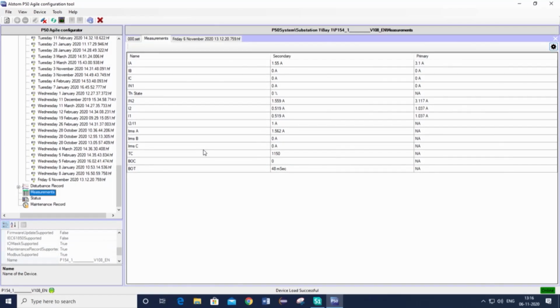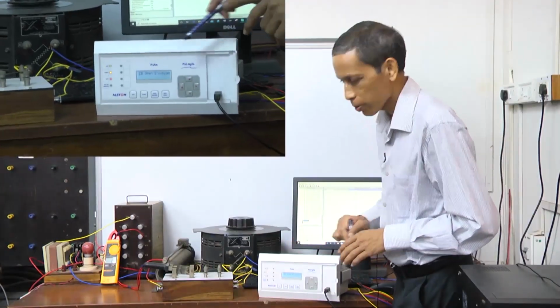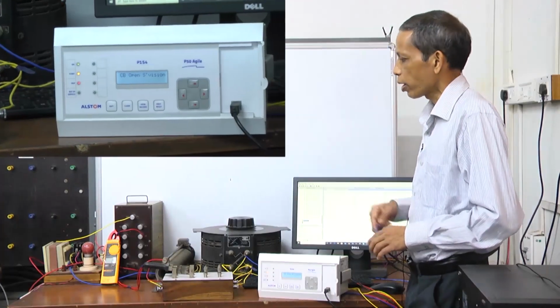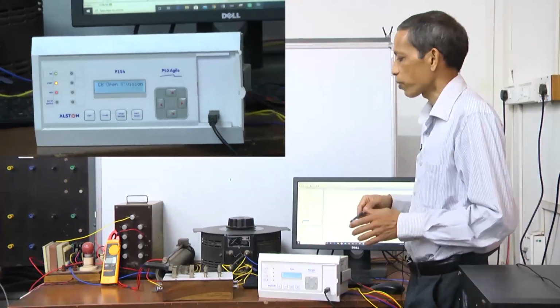So, at more than 3 PSM, the relay trips, as you can see here. Also notice the corresponding trip signal at the relay point, and the bulb flashes on the circuit breaker. This shows that the relay successfully trips this circuit.